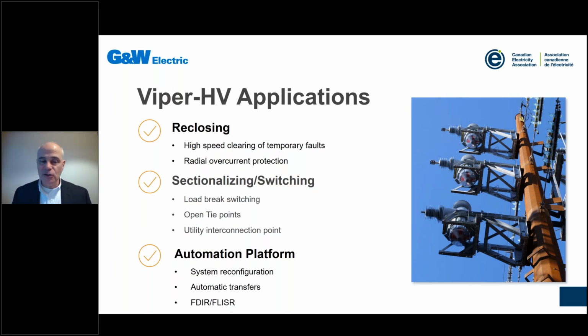That's the legacy solution—typically only met with air disconnect switches, and motorizing them gives some very limited ability to do isolation under a dead-line configuration. Now you can actually deploy real fault detection, enabling complete fault isolation through load break switching.